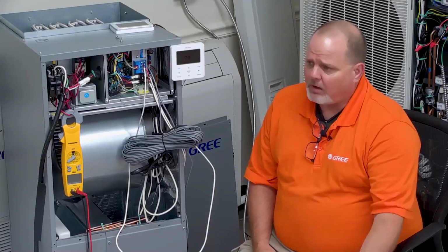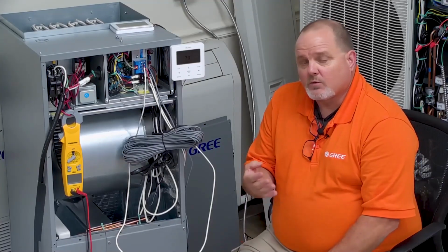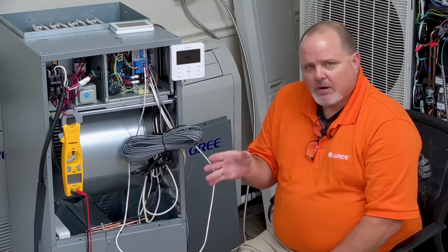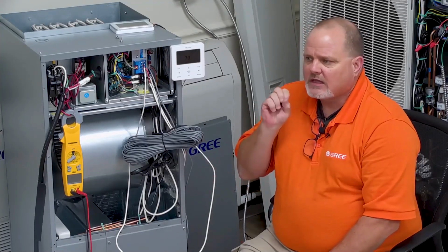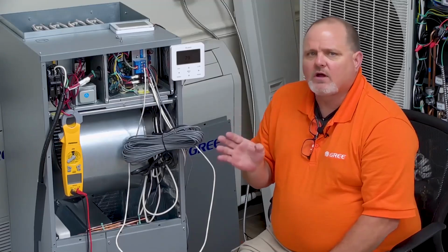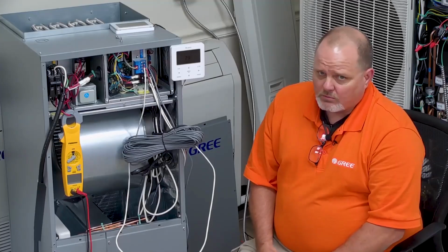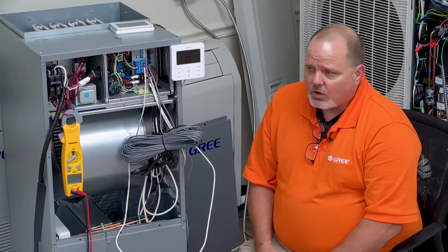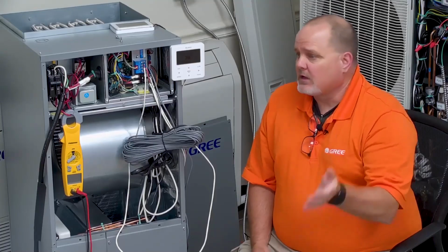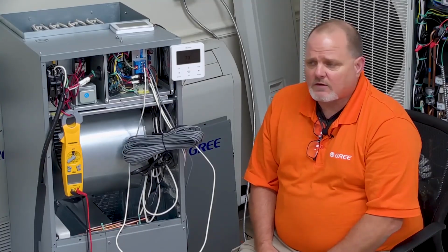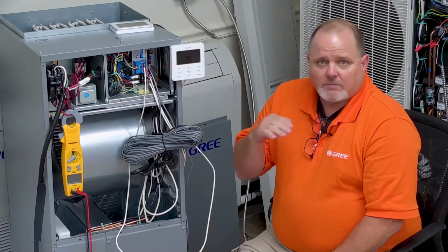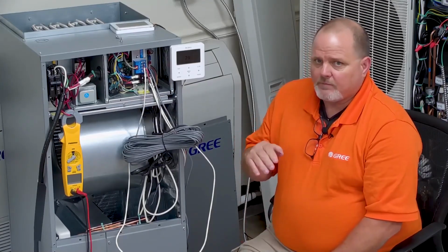Auxiliary heat is exactly that. It's auxiliary to the heat pump. The way it works is the heat pump is heating. That's your first stage of operation. It's heating the home. Let's say it gets cold enough out there, which we all know with the MultiPro Ultra, it's got to get very cold before the heat pump's not keeping up. But even so, let's say you're up in our northern climates and we get some really sub-zero temperatures and wind chills and everything else, and the heat pump slips a little bit and can't keep up anymore. The auxiliary heat function will automatically bring on the electric heat and help the heat pump out.